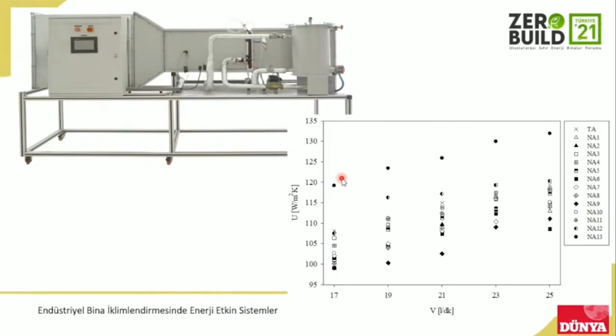It has been a very good presentation. You pointed to important aspects, like where you can achieve success with designs, and you also emphasized shortcomings such as the lack of trained personnel. Also, testing and balancing is another important aspect. There are very good practices and applications, but whether the program systems meet all conditions, or whether the system is actually balanced, is not known. There's not much weight given to this area, and I believe this is important. You choose a frequency controlled pump, but you don't know whether it works within the design ranges. When you don't control it, that means energy is being wasted. These are all important points. Thank you for highlighting them.